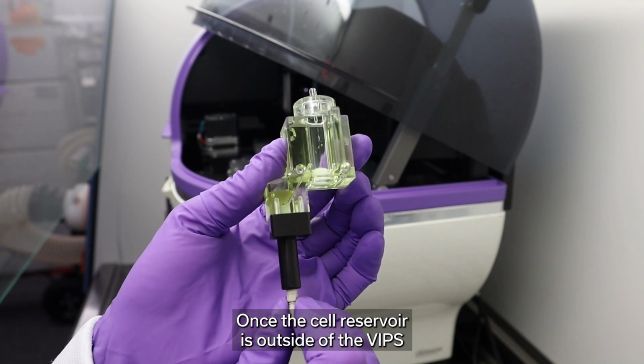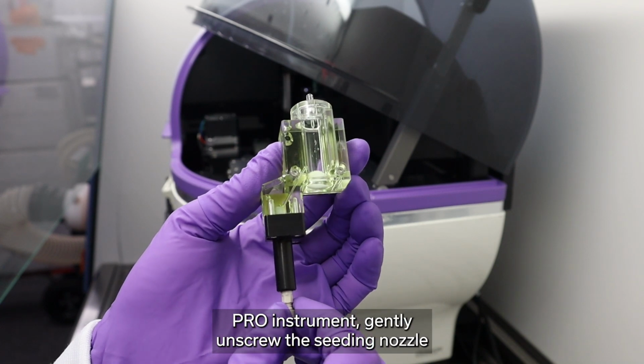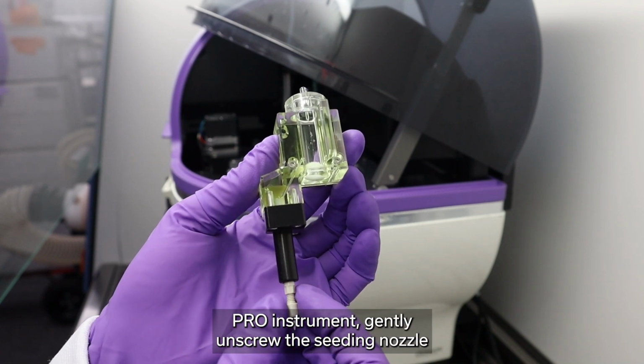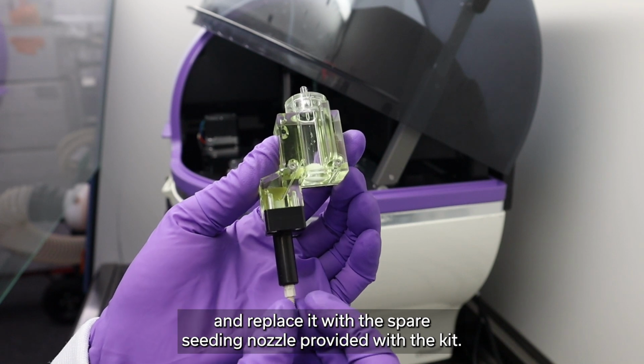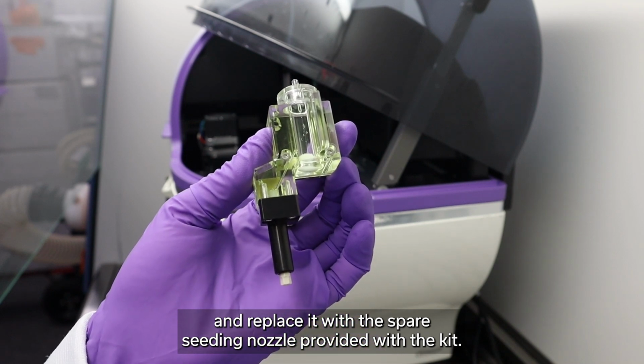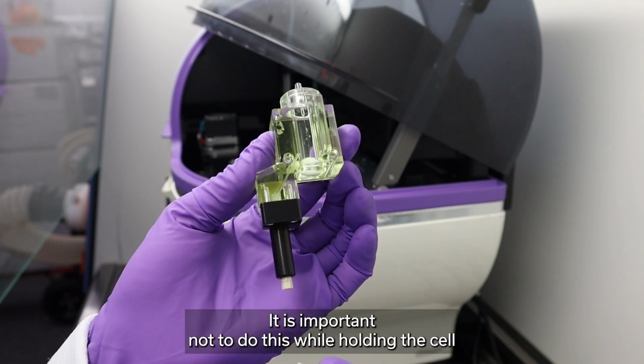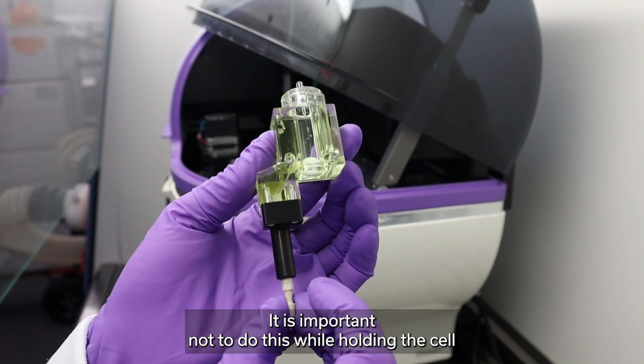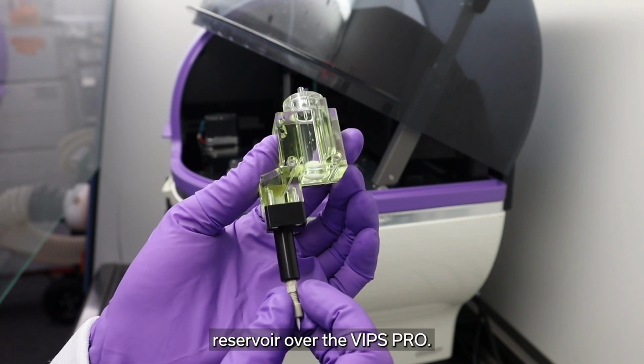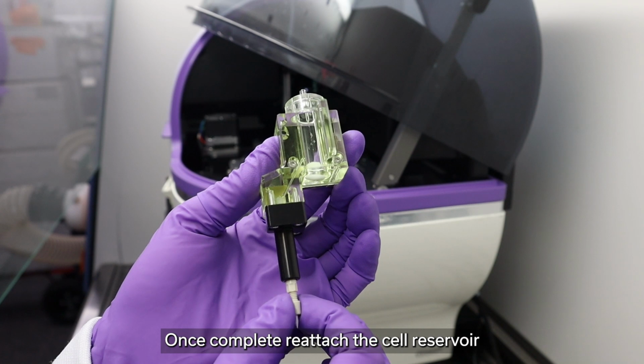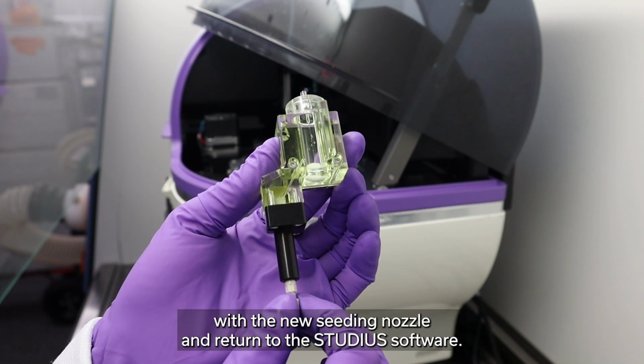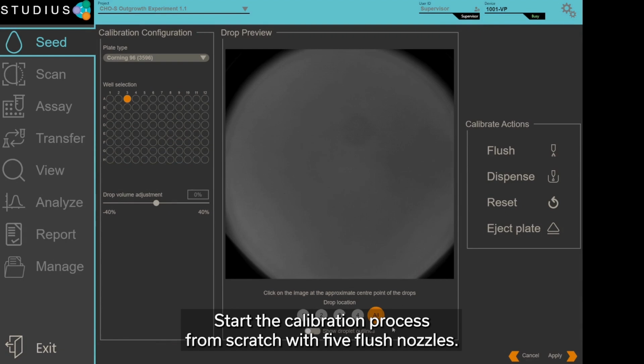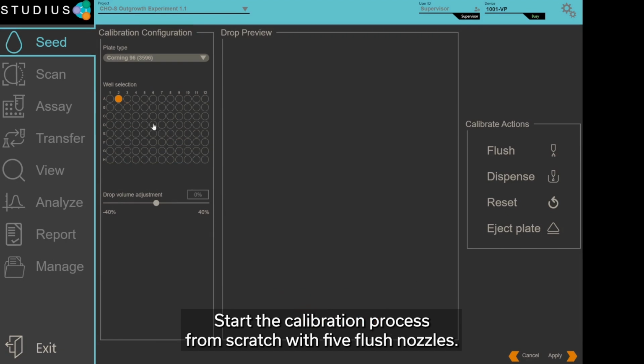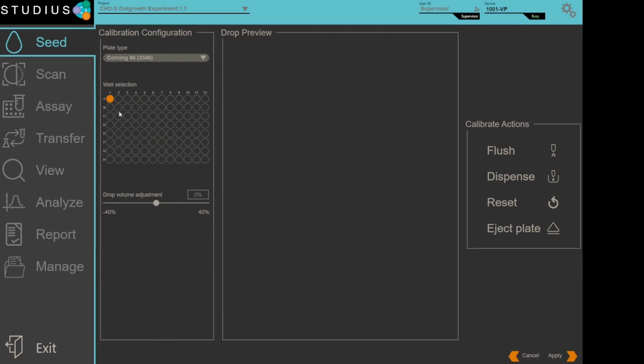Once the cell reservoir is outside of the VIPS Pro instrument, gently unscrew the seeding nozzle and replace it with the spare seeding nozzle provided with the kit. It is important not to do this while holding the cell reservoir over the VIPS Pro. Once complete, reattach the cell reservoir with the new seeding nozzle and return to the Studius software. Start the calibration process from scratch with 5 flush nozzles.